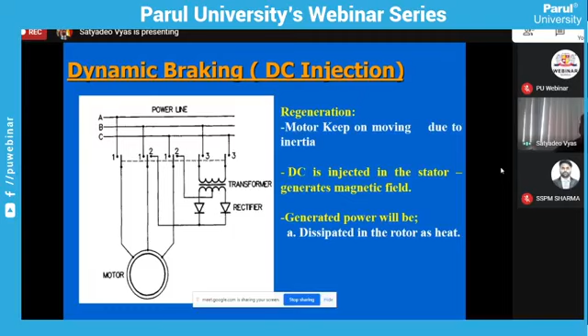VFD is popularly used for power saving. We can use GRR in slip ring motors for power saving and speed control. But in GRR, you have a limitation of speed control. Second, energy loss takes place in the GRR resistance. If input power to the motor is PI, then output power will be PI minus power loss. Power loss in the motor is equal to S into PI. So output power will be input power minus loss. So input power is PI, power loss is S PI. Then mechanical output power will be (1 minus S) into PI. In case of VFD, power loss S PI is very less.